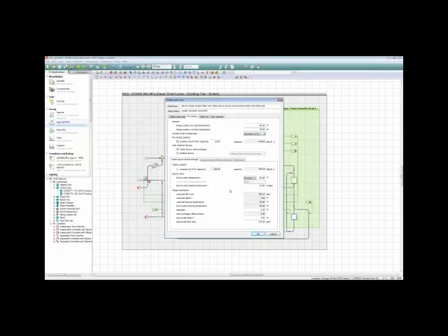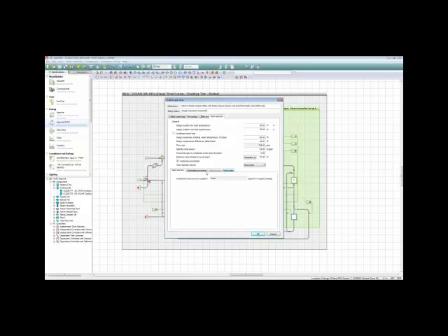And if you have a water side economizer operation, then that will use the cooling tower that is associated with the condenser heat rejection, or in this case a fluid cooler associated with the condenser water heat rejection. So this fluid cooler is on the condenser loop, rejecting heat from the chillers using the water side economizer sort of operation.